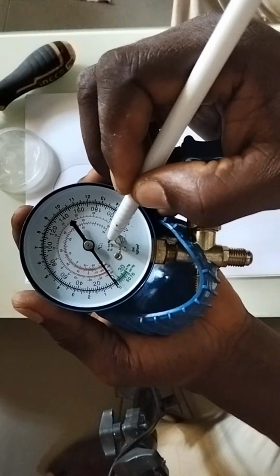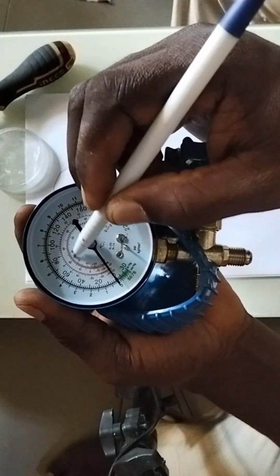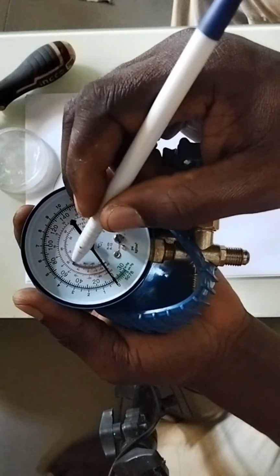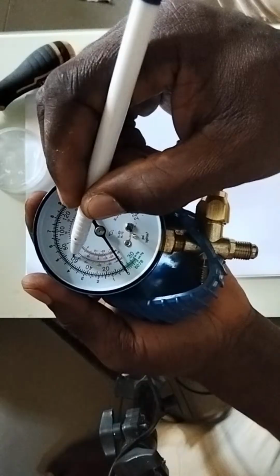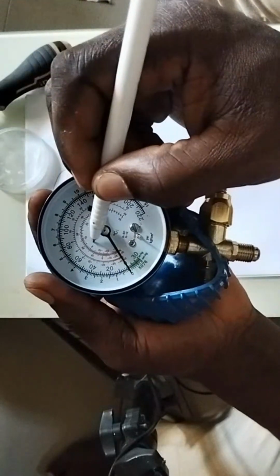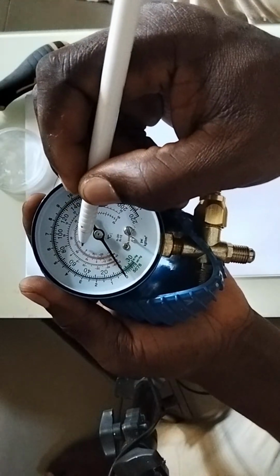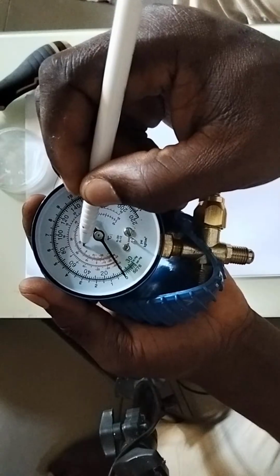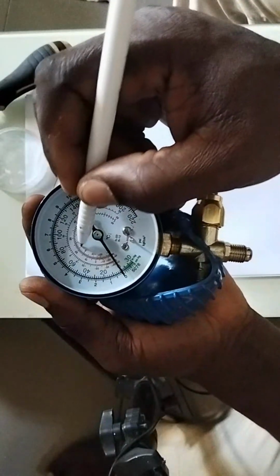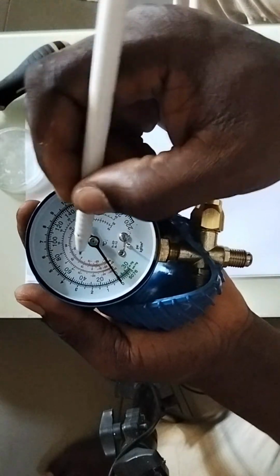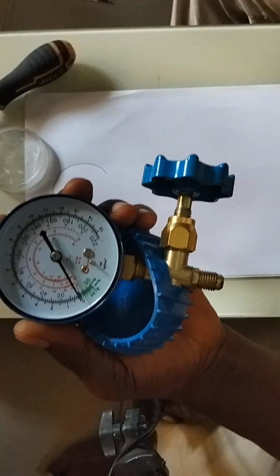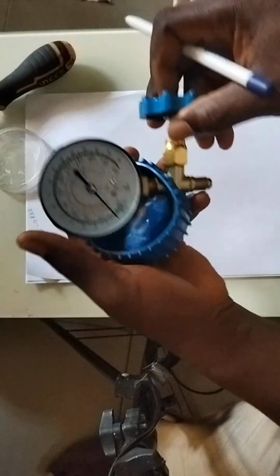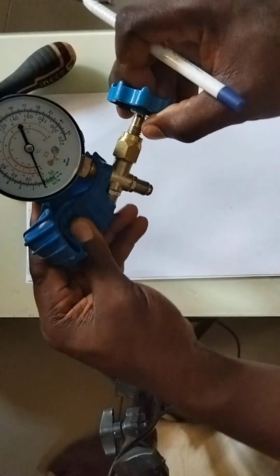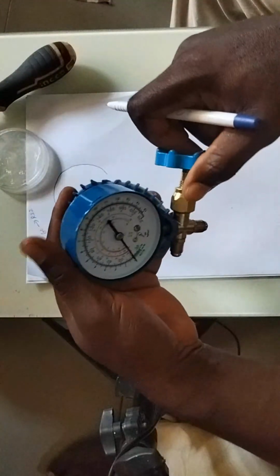If you observe here, the inner calibration is for R22, while the outer calibration is for R12. So if you charge it to about 60 psi, the inner calibration for R22 shows about 5 to 10 degrees Celsius. You get it right? 5 to 10 degrees Celsius. That is the boiling point of R22 refrigerant. So that's how it is. Now, what I need to explain more is about different gases and how to charge them.